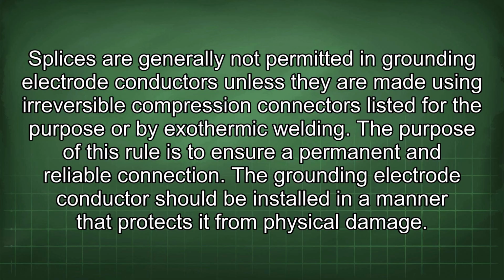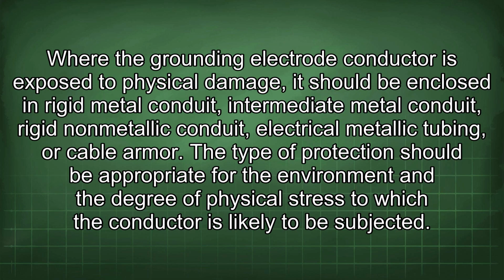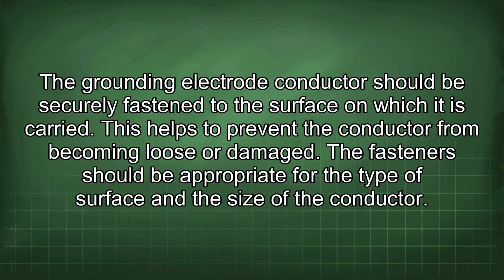The grounding electrode conductor should be installed in a manner that protects it from physical damage. Where the grounding electrode conductor is exposed to physical damage, it should be enclosed in rigid metal conduit, intermediate metal conduit, rigid non-metallic conduit, electrical metallic tubing, or cable armor. The type of protection should be appropriate for the environment and the degree of physical stress to which the conductor is likely to be subjected. The grounding electrode conductor should be securely fastened to the surface on which it is carried.